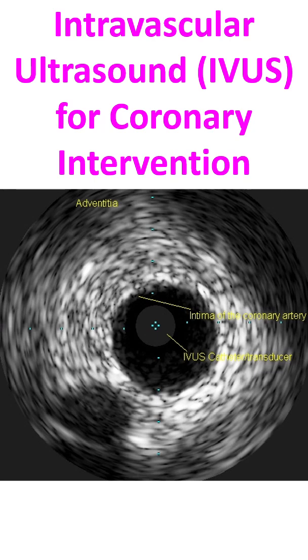Artifacts are possible in an IVUS study due to guide wire artifacts, ring-down artifacts, and non-uniform rotational distortion.